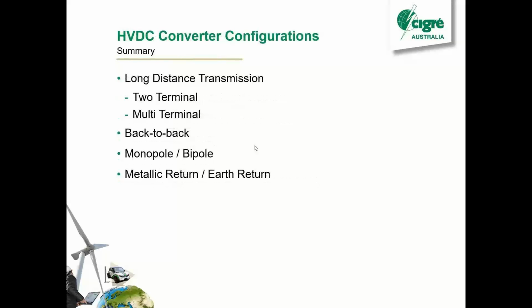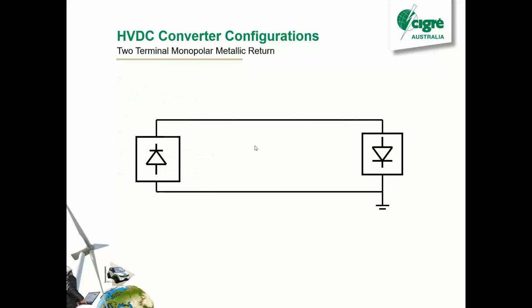All right, so we'll talk about some converter configurations that you can have. Yep, so we'll go through those. So for the long distance transmission, two-terminal. I just have to say for the LCC, two-terminal is pretty much 99% of the installations in the world. You'll have a sending end and a receiving end, and yeah, you can change it around if you want, depending on your circumstances. In New Zealand, we do change the power direction quite a bit, about 30% of the time might be going south, but 70% would be going north. But some other schemes will only ever go in one direction, because there might be a big generator at one end and a load at the other, so you're never going to do reverse power.